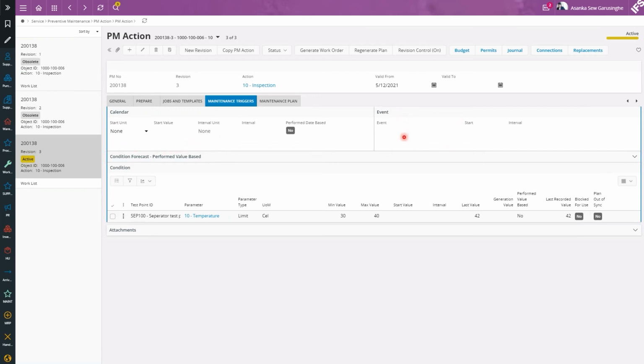Then you have event triggers. For example, if you want to maintain certain objects only when there is a total facility shutdown, you can define an event for a shutdown and attach it to the PM action. When the shutdown actually takes place, like at year end or during the holiday season, you can declare the shutdown using the system, and that would generate work orders.